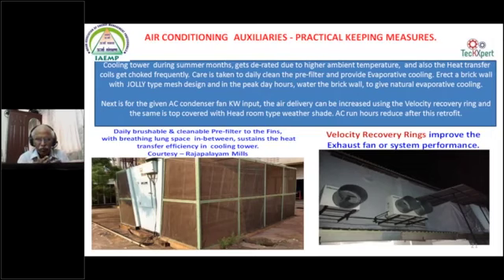On the air-cooled condenser, I am putting a velocity recovery ring. Again I am telling, these are all low-cost innovations, low-cost retrofits that can be done to improve the air coverage for the given fan, for the given kilowatt given to the air-cooled condenser. It can be on a package, it can be on a duct, or it can be on a split machine also.